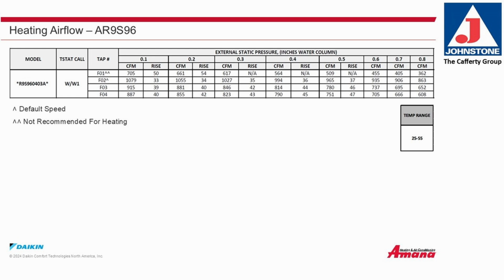Heating airflow. In this example, we'll look at the AR9S96 furnace. On this chart, we'll examine external static pressure in inches of water column and its effect on CFM and temperature rise at a specific fan speed. I've highlighted the top line, which shows the ESP ranging from 0.1 to 0.8 inches water column. I've also highlighted the default fan speed for this furnace. You can see how the external static pressure affects the CFM and temperature rise at a specific fan speed.